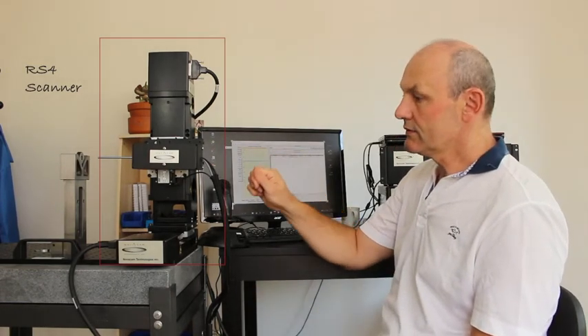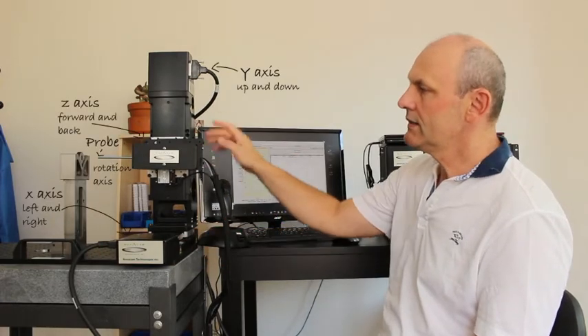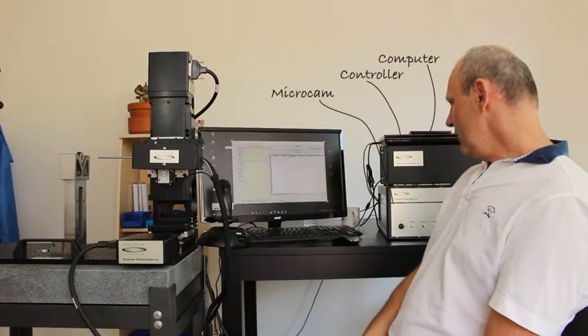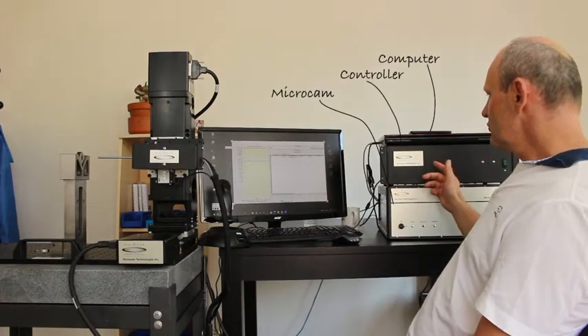And it consists of four axes, the X, Y, Z, and the rotation axis in the front, which makes the probe rotate inside the bore. And over here we have the microcam and the motion controller and the PC.